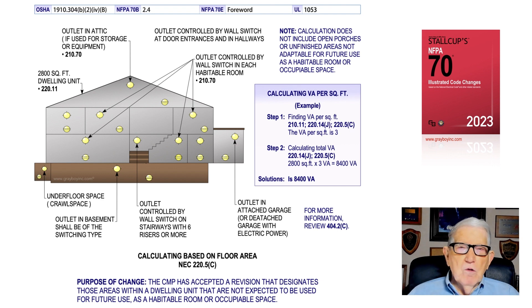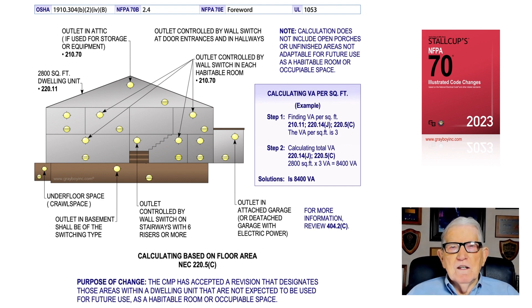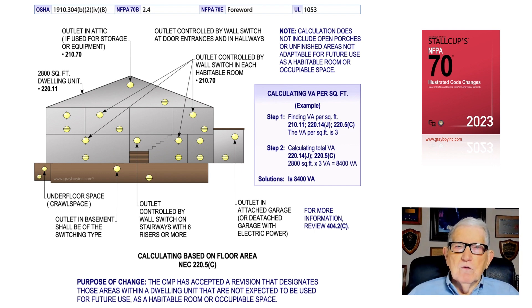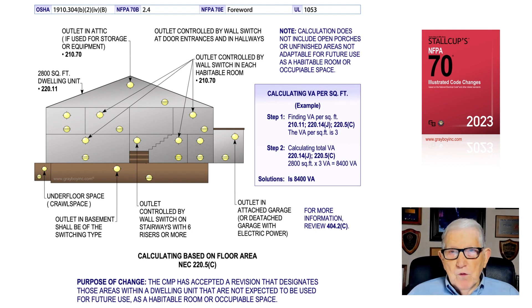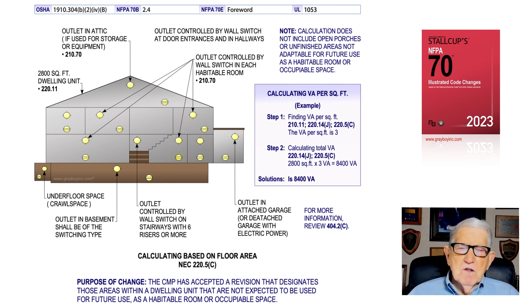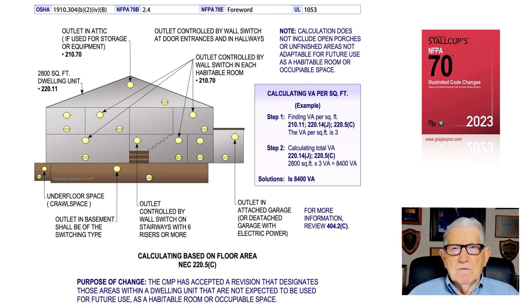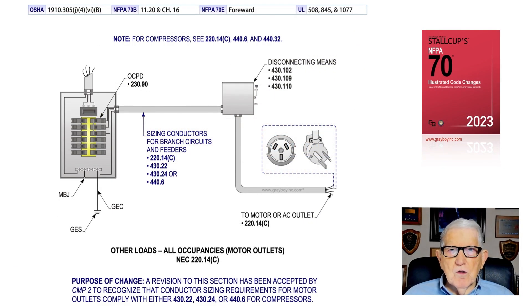Step two: we take 3 VA per square foot — 3 VA times 2,800 — we come up with 8,400 VA. That total VA rating is used for all the lighting and branch circuits that do not include the small appliance circuits and direct circuit loads routed in the dwelling unit to special pieces of equipment. There are additional call-outs you can review for a real case study calculating loads based upon floor area pertaining to a dwelling unit.